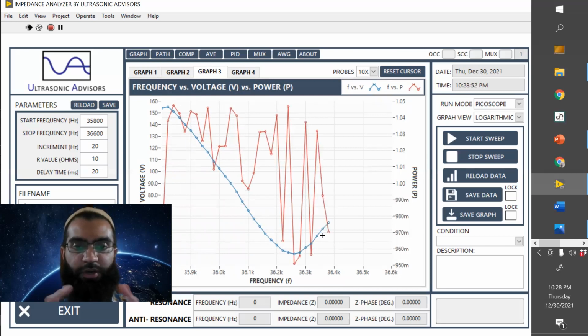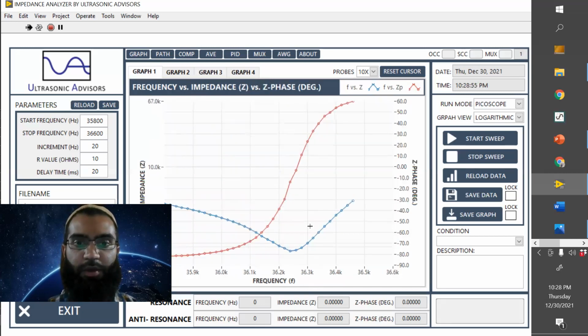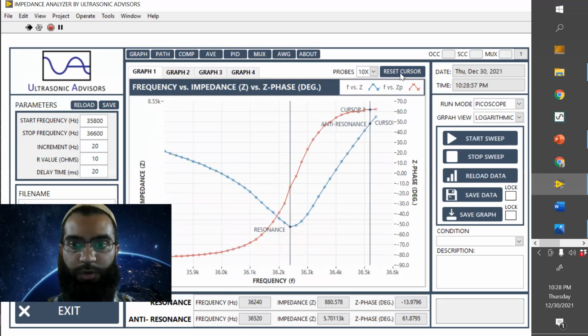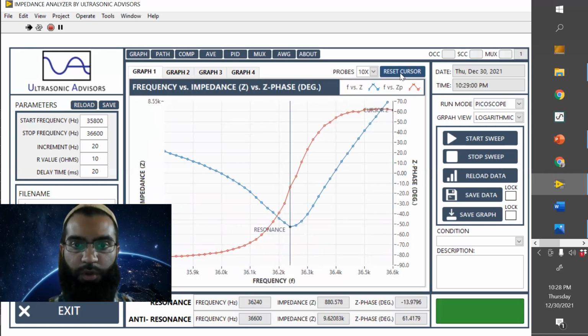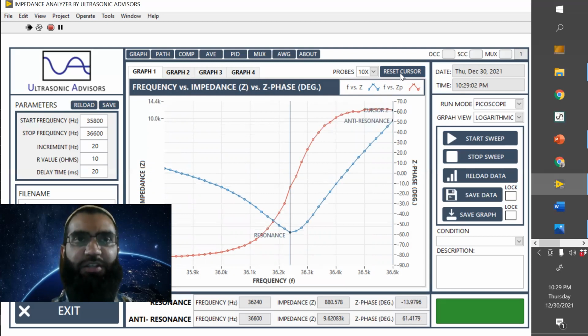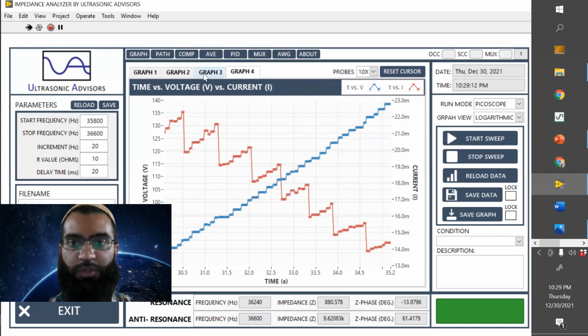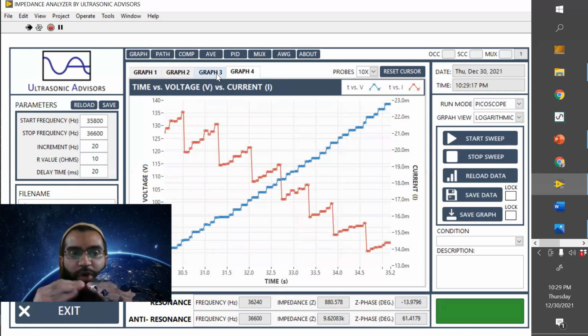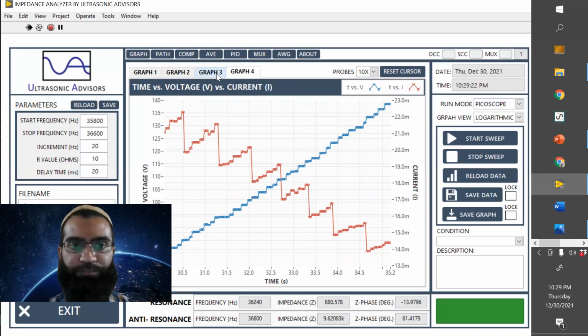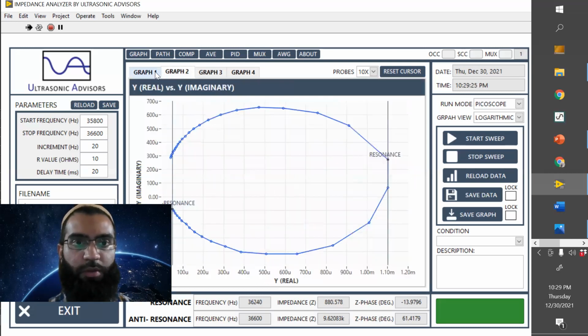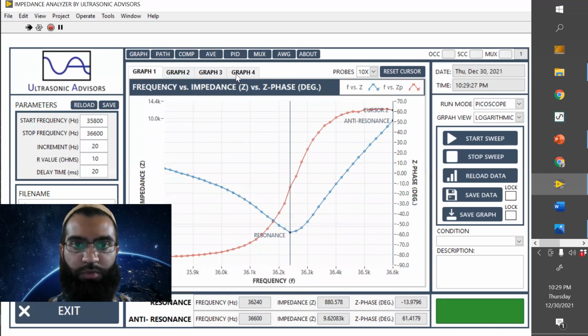And that's a good, nice symmetrical resonance happening there. With the tool on, I think the tool adds a lot of impedance, and so does the holding mechanism. Therefore, we're not really able to excite this with a lot of power and get my expected trend, which is what I've seen in many other transducers. As you increase power, you'll reduce in impedance. So this didn't really happen.